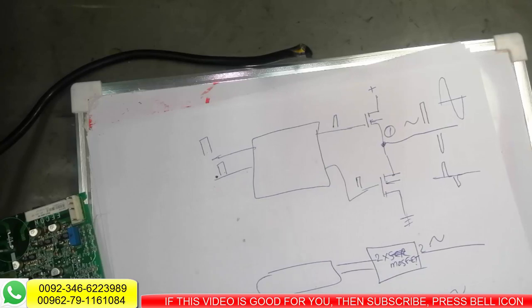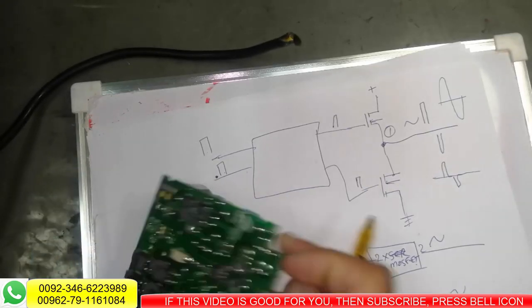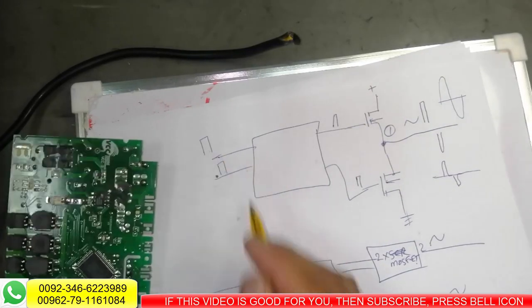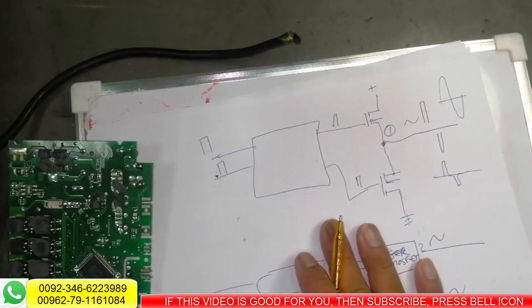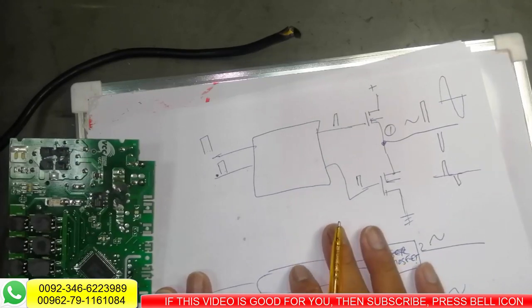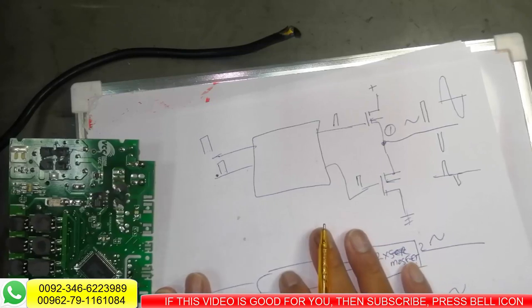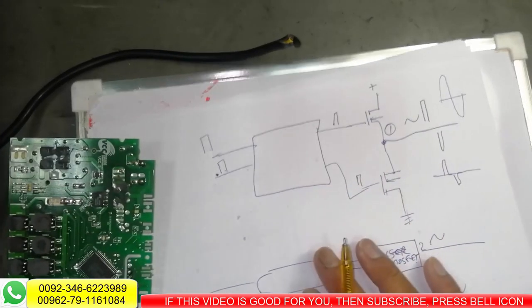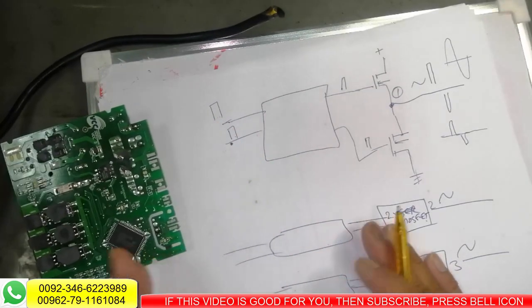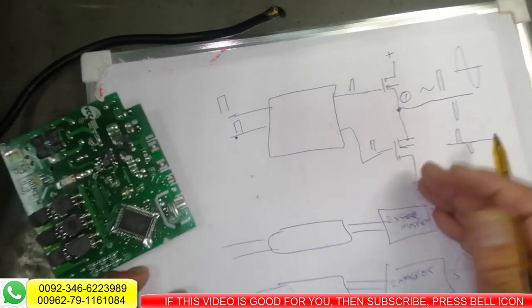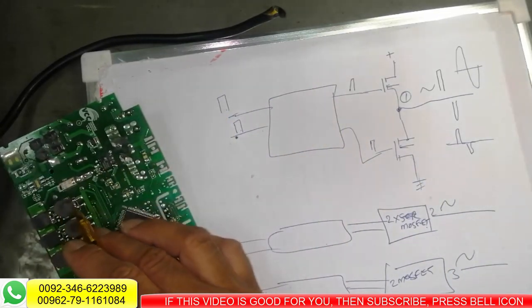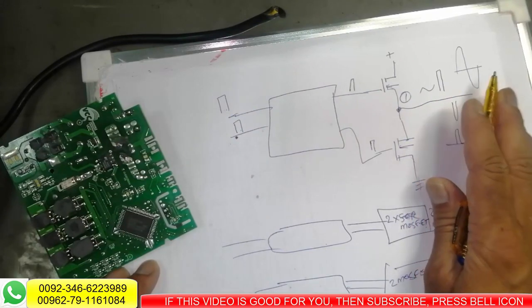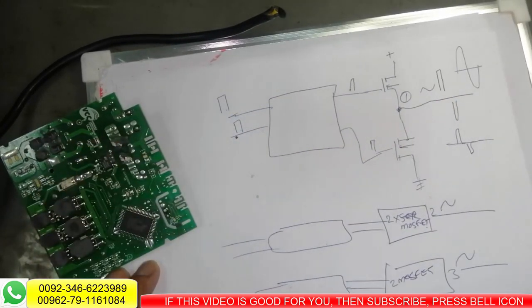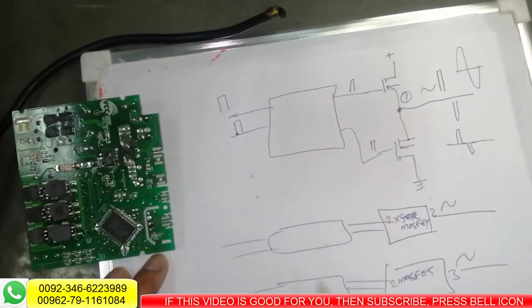Every IC has two drivers, high and low drivers, and it is controlled by the processor. This frequency is controlled by the processor. Here is a different technology. In this board, it is not a pulse width modulator. Here it is a change in frequency. There are two technologies, change in frequency or change in pulse width. Here the pulse width will remain the same, but the frequency of the pulses will change. The processor will calculate the required frequency at the output, so in this way it makes the switching time period different.